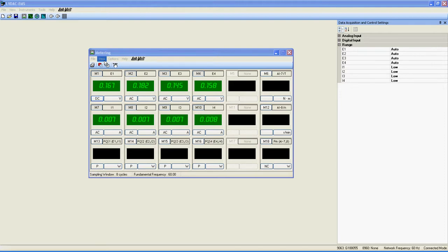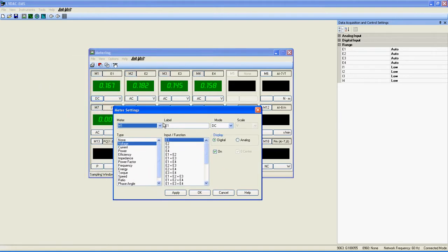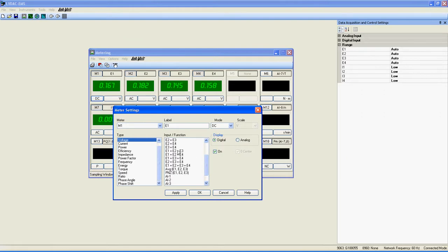Now, let's learn how to configure a meter. First, click on View, then on Meter Settings. This new window is where you choose what will be displayed on each meter. Here is the meter's number and the meter's label. You get a very impressive quantity of value types, and for each of them, a large quantity of inputs or functions. For example, for the value type voltage, you get inputs E1 to E4 plus a lot of functions associated with those inputs. A single meter can give you the sum of inputs E1, E2, and E3. To set a meter to a desired configuration, click on the type you want, click on the input or function you need, and then click on Apply.